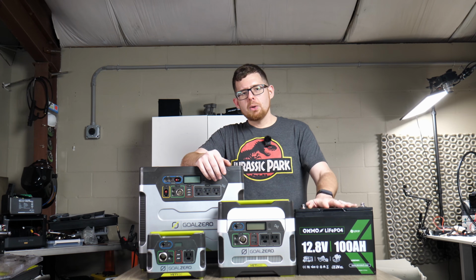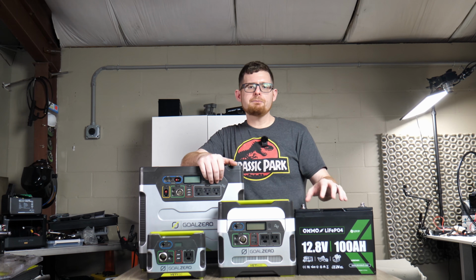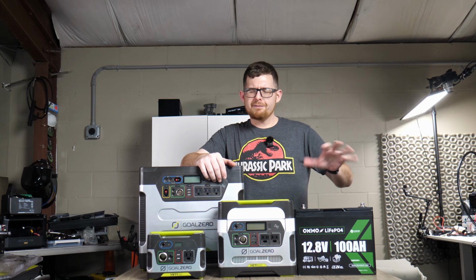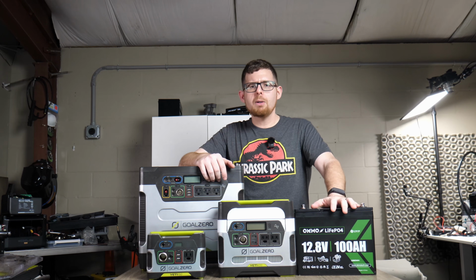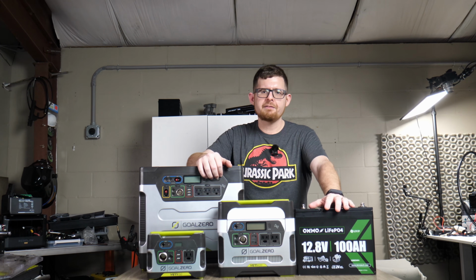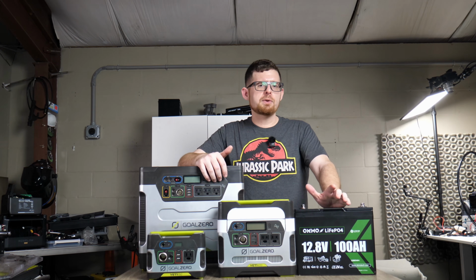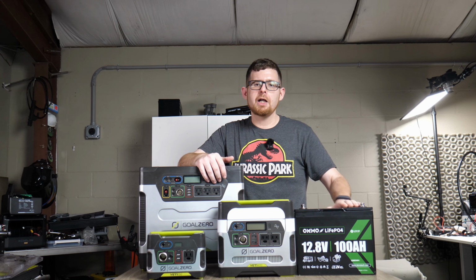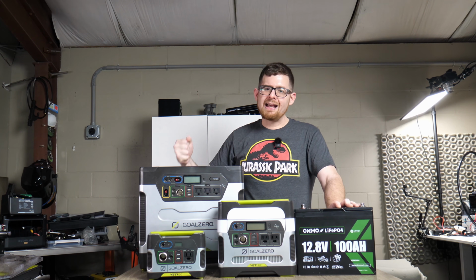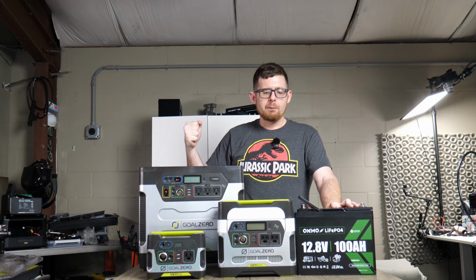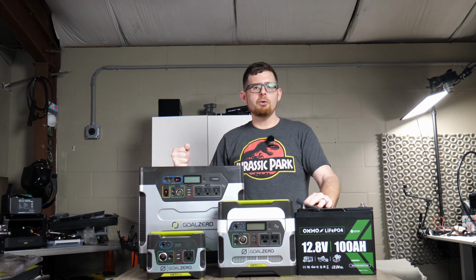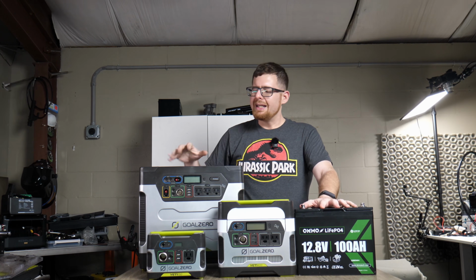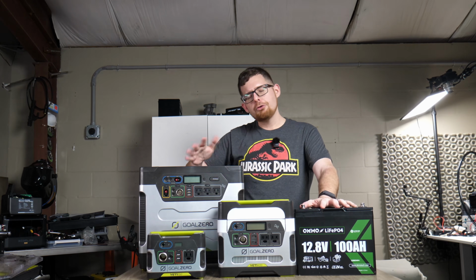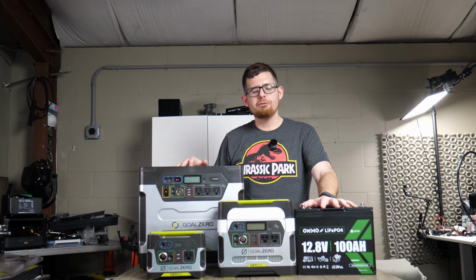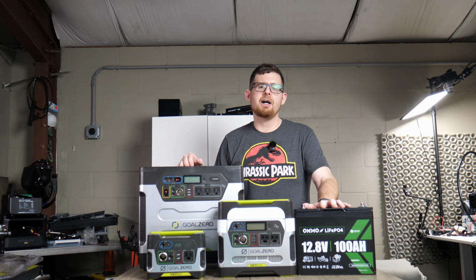The charge, though, on this one can go up to as high as 14.6 volts. It's actually rated at 14.4, but there's a plus or minus 0.2 volt variance allowed, so it can go up to 14.6 volts before the BMS is going to cut charging off. And that's almost exactly what one of these units will do. It will push out around 14 volts to charge this up to its max, and it will discharge it down to around 11 to 10.5 volts, which is a safe limit for lithium iron phosphate.